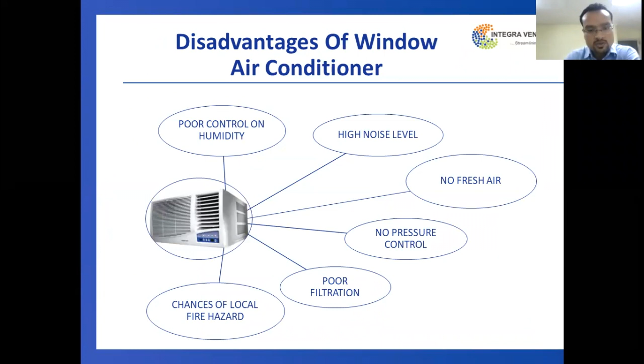Disadvantages of window air conditioners include poor control, high noise level, no fresh air, no pressure control, poor filtration, and chances of local fire hazards. So we need to avoid this in hospitals.